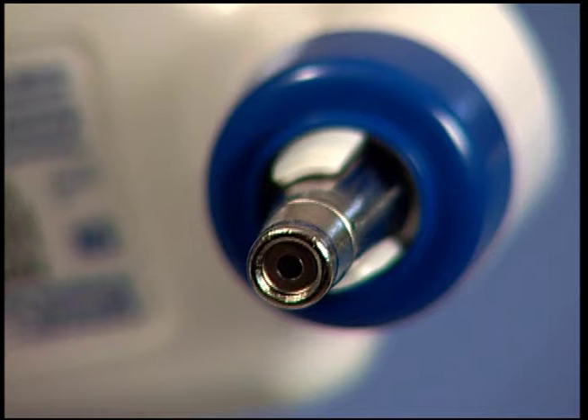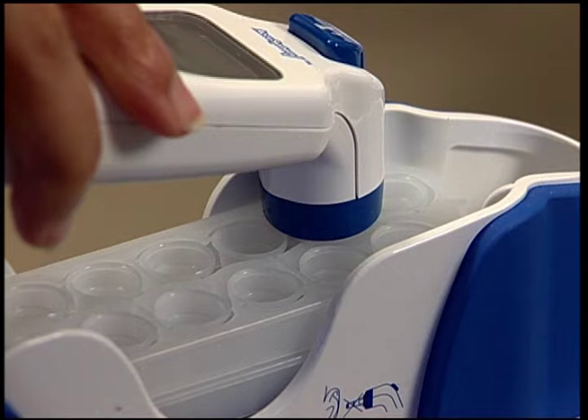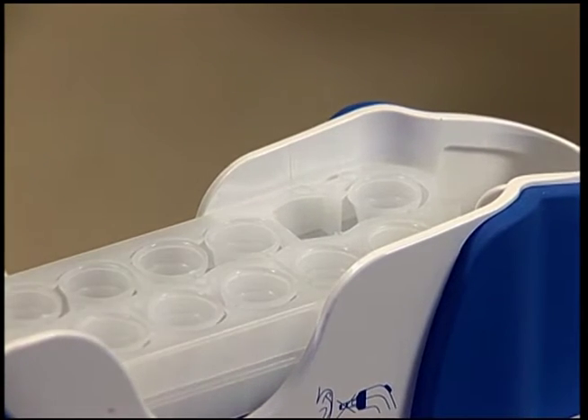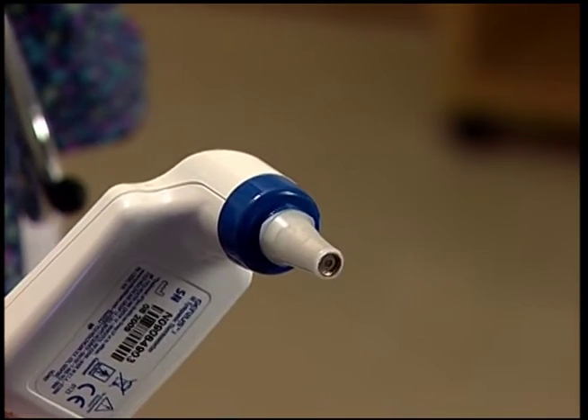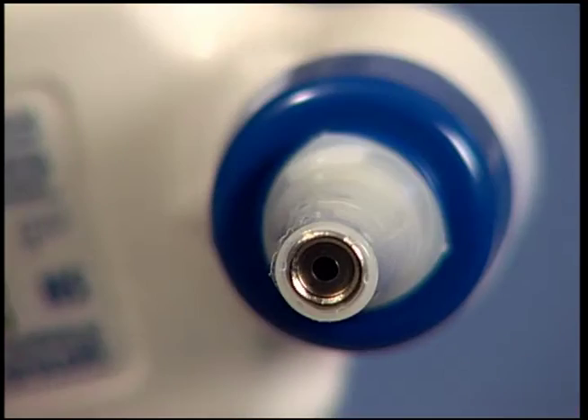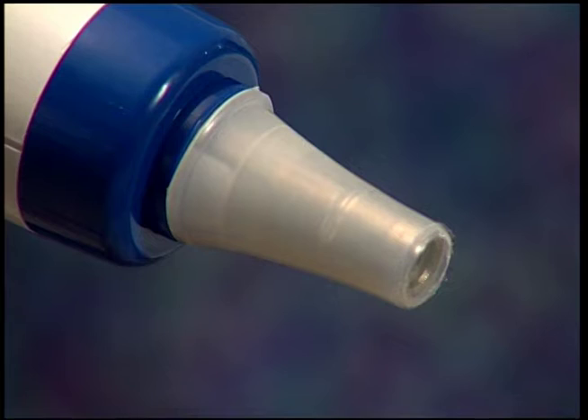Inspect the probe lens to see that it is clean and free of cracks or debris. Push the probe tip straight down into a probe cover until you hear the click. Lift the Genius 2 out of the cassette with the plastic probe cover attached. Check to make sure the membrane on the end of the probe cover is smooth and the cover is securely attached. If there are any visual holes, tears, or wrinkles, discard and attach a new probe. You will know the probe cover is attached securely if the silver probe tip is completely covered. An improperly attached probe cover will not take accurate readings.